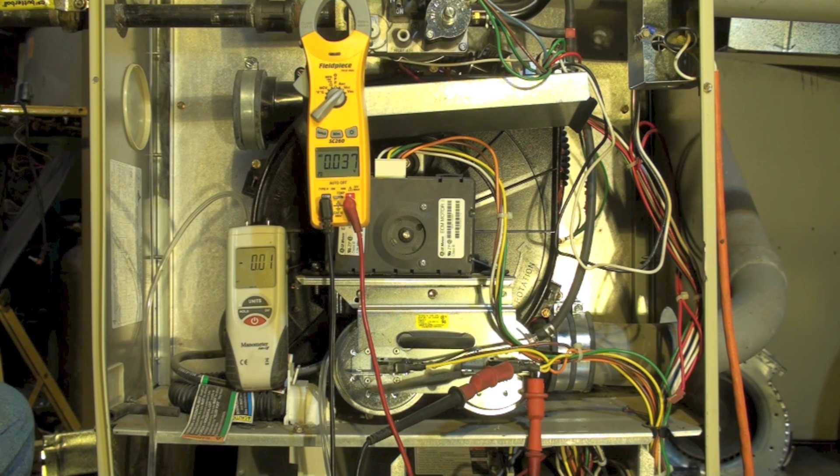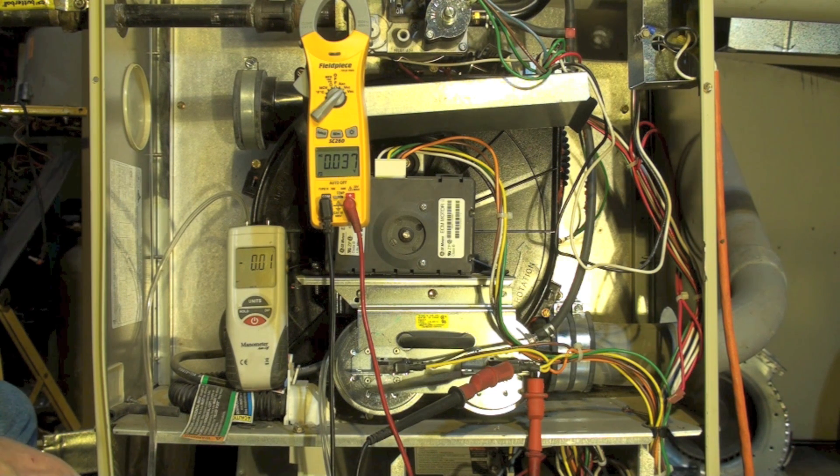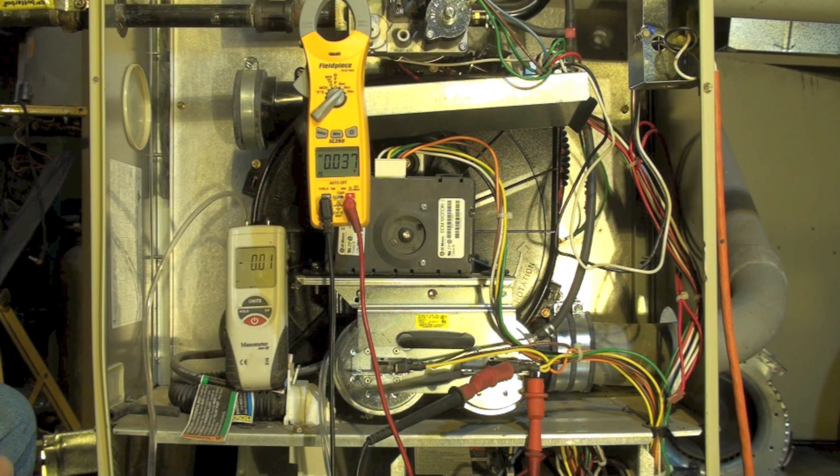This meter here is going to give me the vacuum that is inside the furnace. Now what this inducer is going to do, because it's a variable speed inducer, is it is going to match the negative pressure in the vent to the venting. If it's not a variable speed, it just goes up to a certain amount and if the venting is clear it makes. What this does is adjust the inducer speed or the vacuum. The inducer speed creates a vacuum. It adjusts that speed to the venting.